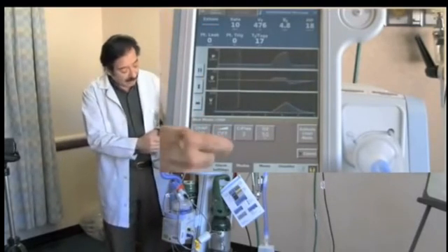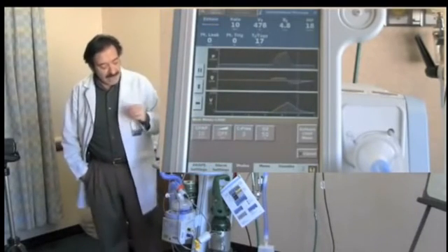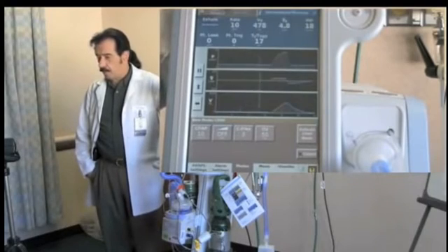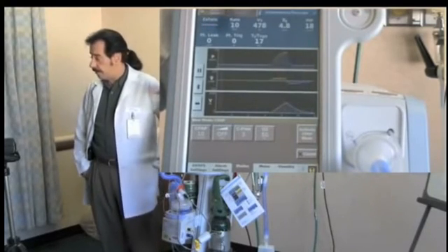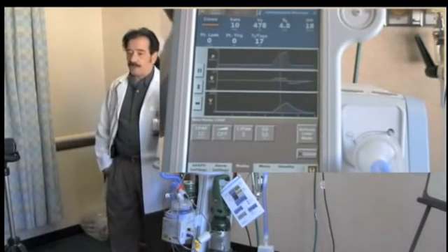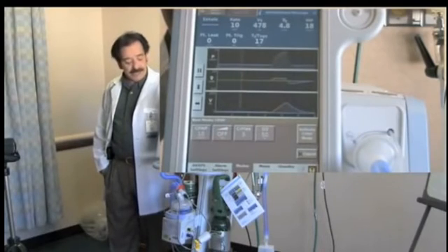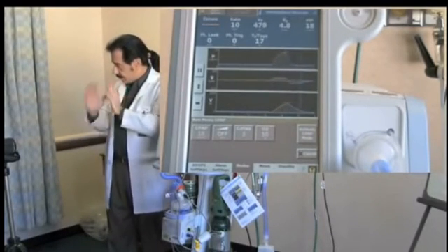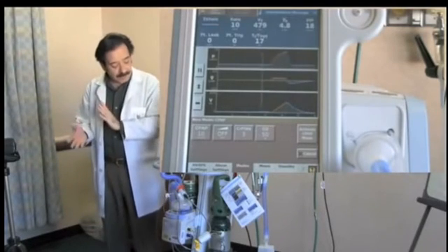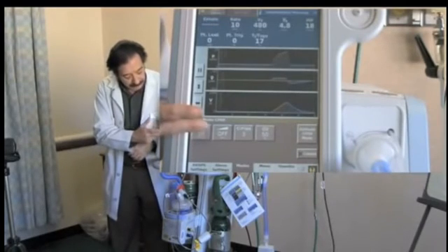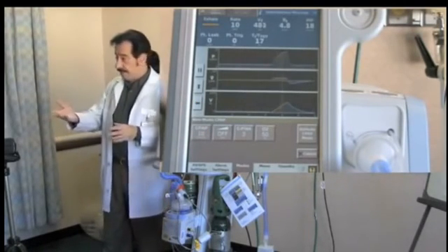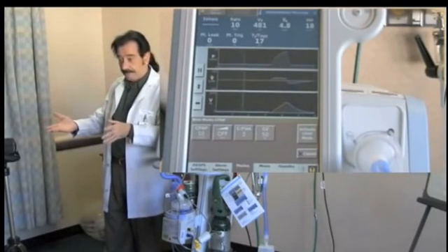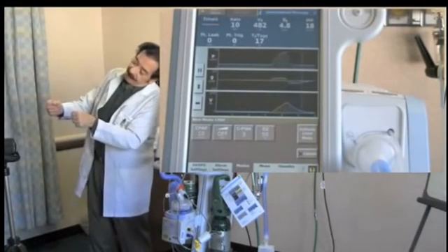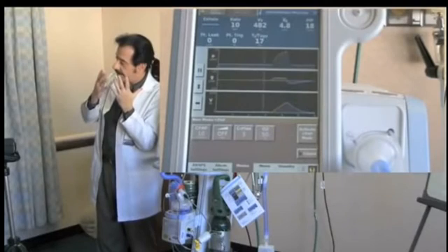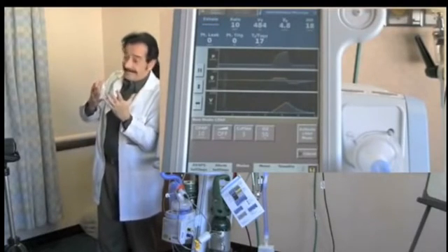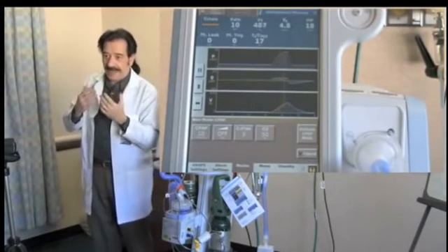There is a new adjunct on this device, and it's called C-Flex. Now, the Respironics devices are noted for their triggering and cycling algorithm that's called AutoTrack. And AutoTrack is one of the best methods in the industry to know when the patient's in an inspiratory phase and when they switch over to the expiratory phase. It can really keep up with the patient. Now, say I have a high CPAP level, here's 10. The analogy is I'm driving in a sports car at 100 miles an hour down the Autobahn. And I roll the window down, and while I'm driving, I stick my head out the window, and I have a 100 mile an hour wind hit me in the face. Now, when I open my mouth to take a breath in, boy, that's easy. 100 mile an hour winds flowing down my airway, and breathing in is easy.